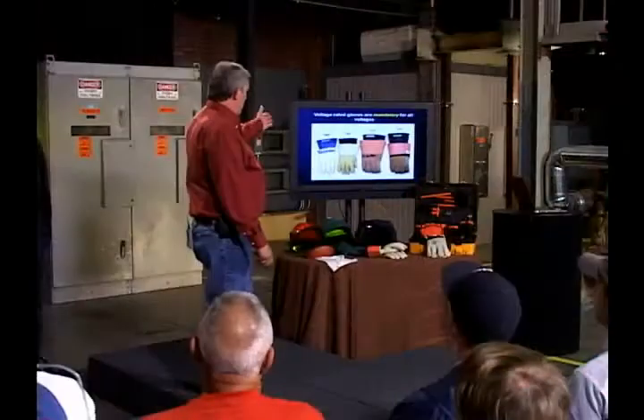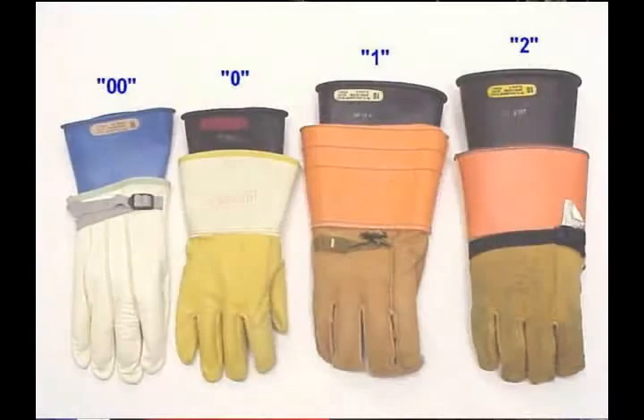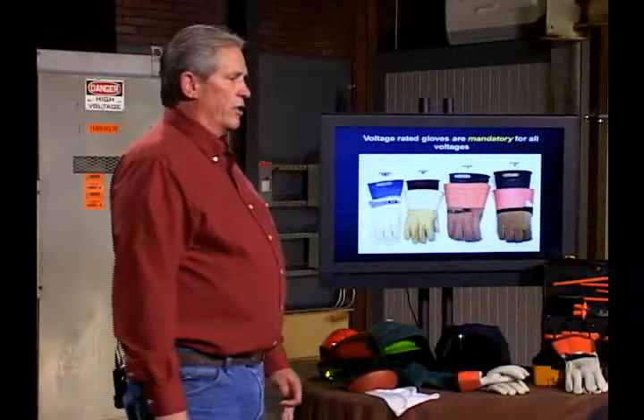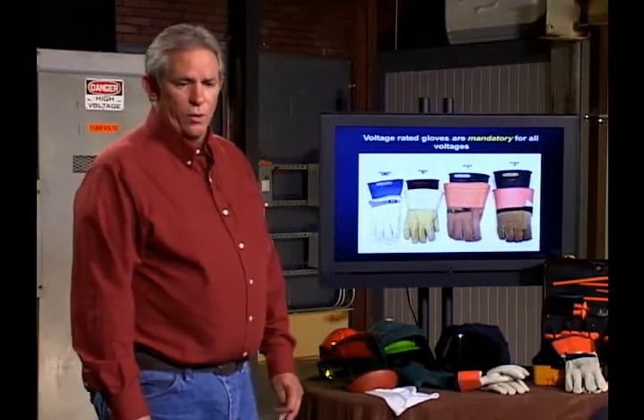Here are the gloves in a pictorial format: double aught, the first one. The second one is aught, rated for 1,000 volts. The 1 is rated for 7,500 and 2 rated for 17,000. Now these gloves must be tested every 6 months by an independent certified laboratory. And they must be tested and checked by you every time you use them for air leaks or any kind of defects in the glove.